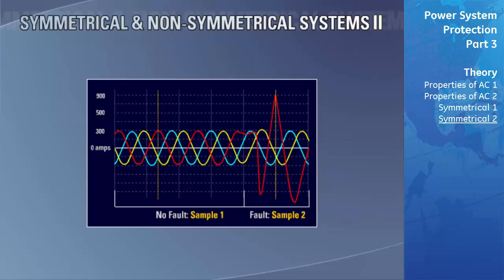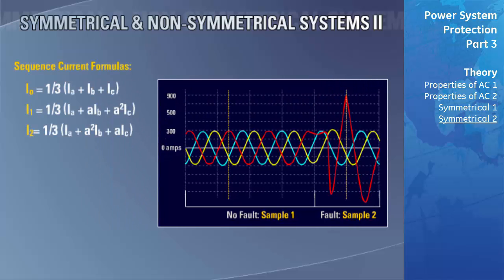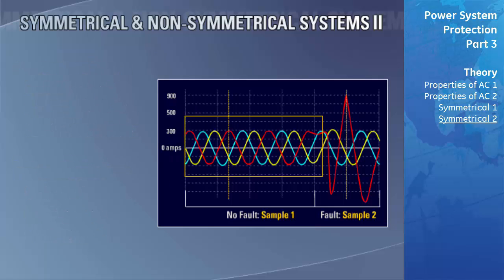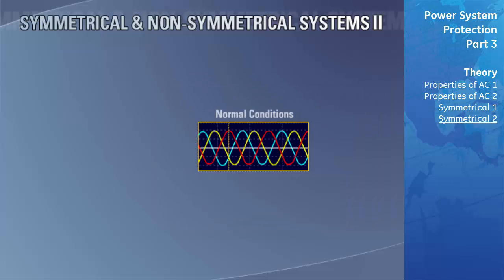Sample 1 data is prior to the fault, while sample 2 data is during the fault. Since we know the values of Ia, Ib, and Ic, we use the displayed equations to calculate the sequence current quantities at sample 1 and sample 2. Once the sequence components are calculated, the unbalanced currents of phase A will be recalculated using the displayed formulas to verify the results. Under normal conditions, power is generated and distributed as a balanced system, possessing only positive sequence currents and voltages according to Fortescue.